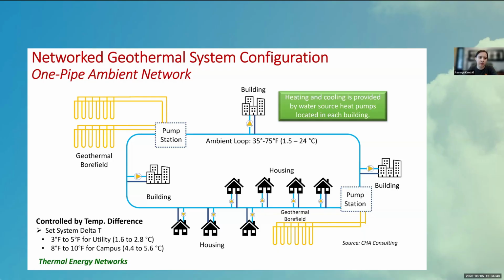With a focus on the temperature differential that Chris was talking about earlier, the whole system and the pumping rates are controlled by the delta T, or the temperature difference across the heat pumps. For a utility, this is typically going to be a little lower. For a campus system like a university campus, it might be a little bit higher, but I'll get to that in just a moment.